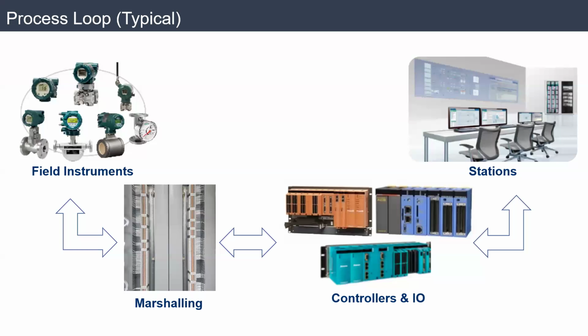Okay, next. As we just explained, now the field instrument will come to the marshalling. As you can see in the marshalling, you will have terminal blocks. You can see on the left side the field cables coming here. For each signal, you'll have two cables, plus and minus. It will become on these terminal blocks. They call them TBs. And then from the TBs, it will go to the controller. As you can see here, we have three types of controller: DCS, ESD, and RTU. DCS is for controlling the full plant.